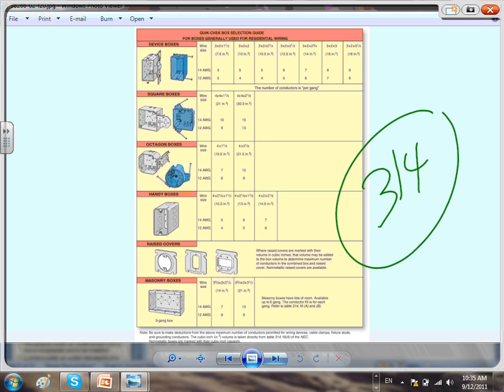It really comes in handy for metallic boxes. Non-metallic boxes, if you open them, right at the back they're stamped with the number of conductors and/or the cubic inches they have in them. So if you have the cubic inches, you do the calculation - we will do at least one example since you guys have done that before.